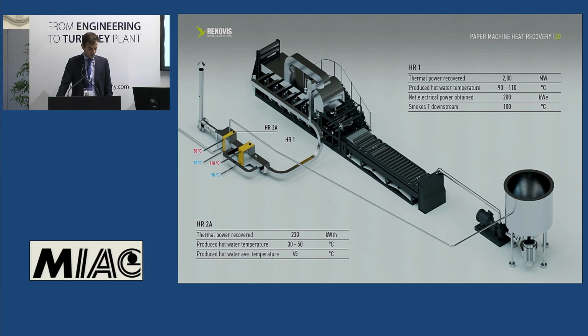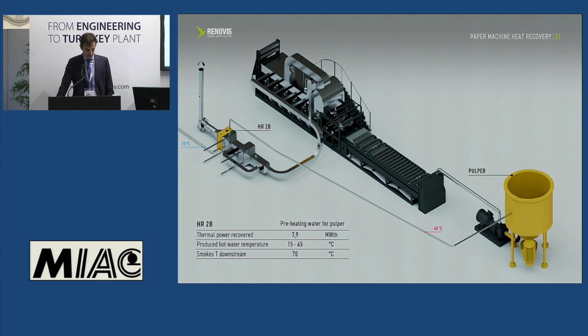The superheated water is used to power an organic Rankine cycle turbine to produce electricity. The second stage instead delivers hot water at a lower temperature, useful for the felt-forming section of the paper machine itself. The thermal power developed in this stage is about 230 thermal kilowatts. By means of the third and last heat exchanging stage, we can produce hot water to be used in the pulper as well, in the form of hot water at not more than 45 Celsius degrees. The thermal power obtainable is really significant. As you can see, it touches almost 8 megawatts of thermal power recovered.